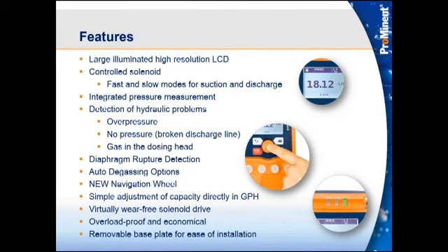What it does is I put the pump into automatic mode. Once I do that, if you're familiar with our pumps, on the screen you usually are able to see the stroke length and the frequency on the main screen when you're navigating through. When I put the pump into automatic mode, it takes those selections away from me. I can no longer see what the pump's frequency is doing or what the stroke length is set at. What automatic mode does is, on the main screen, it's going to show me in gallons per hour what the pump is currently set to pump at.